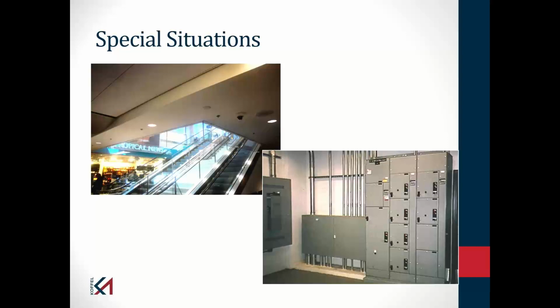Other things that I see on college campuses would be the protection of escalator openings, or maybe even larger openings. In a lot of the student union buildings, I'll see these large vertical openings that the building codes call an atrium. So do I need to have sprinklers around that space? Do I need to closely space sprinklers around that space? It's a little hard to pick up in that photo, but there is a clear draft curtain around that space designed to prevent the smoke from going up through that vertical opening until the sprinklers can operate and control the fire and cool that smoke. Therefore, the smoke would be less buoyant.